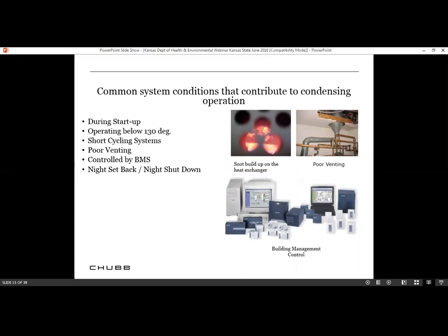Common system conditions that contribute to condensing operations are during startup, operating below 130 degrees, and that's because of the dew point of the water. Short cycling systems, and that's basically where the boiler comes on, comes off, comes on, comes off several times and cycles all the time, and that affects the efficiency. Poor venting, if you look at the far right there, you'll see the way that system was vented was incorrect.